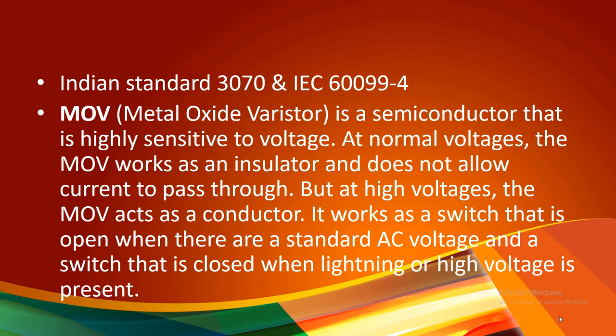Now if we look at the MOV — metal oxide varistor — it is a semiconductor. It behaves as both a semiconductor and an insulator. The MOV blocks have a rated voltage, which is the normal voltage for which the surge arrester is designed. For example, if we designed the surge arrester for 9 kV, that is the rated voltage.